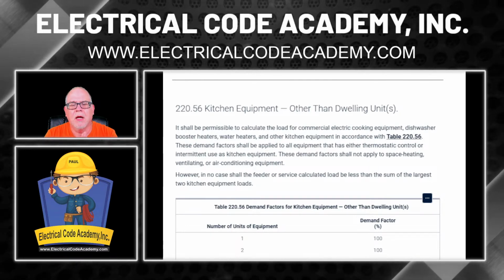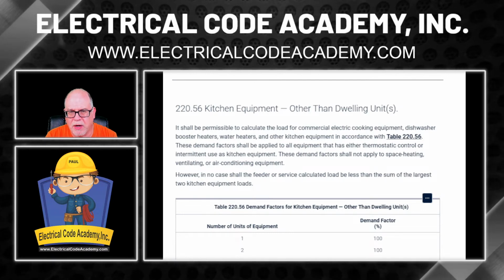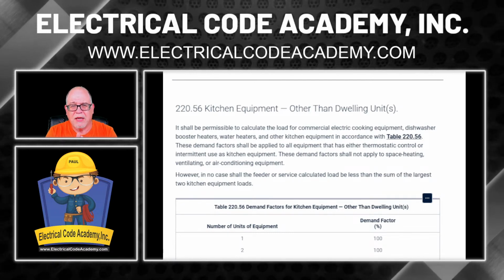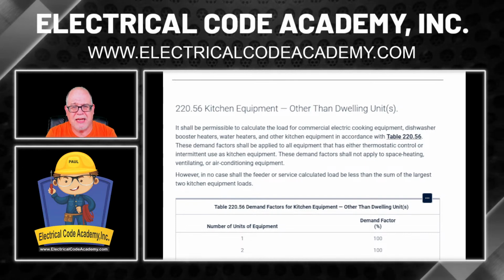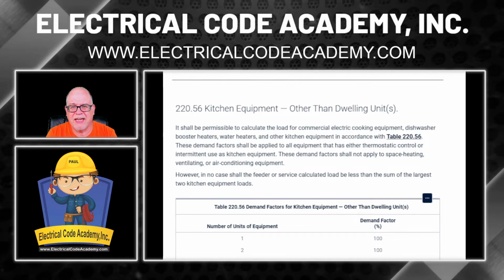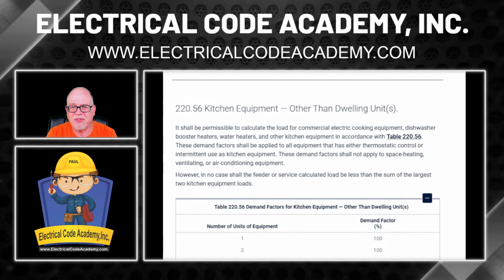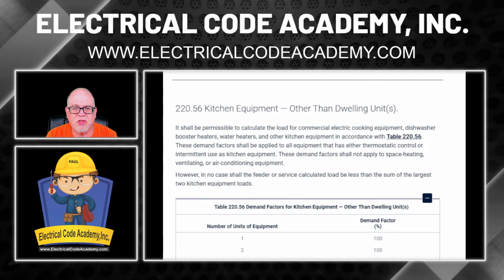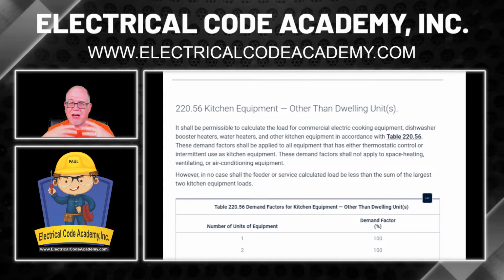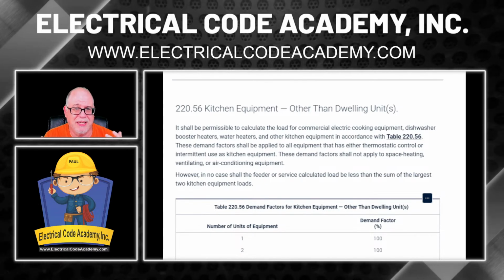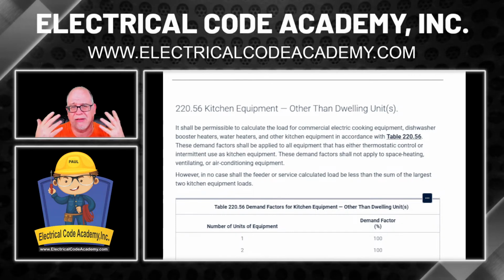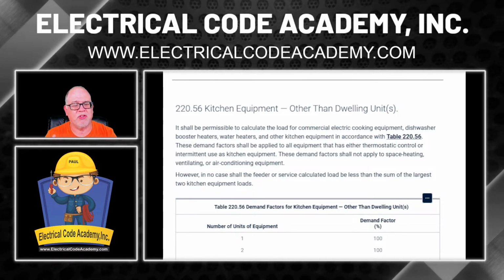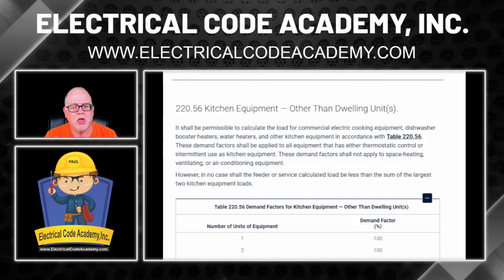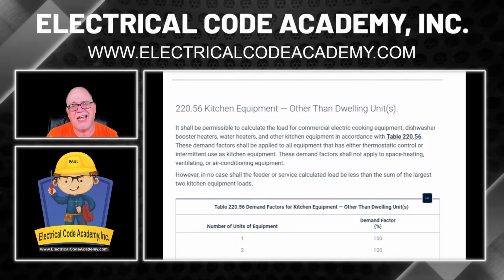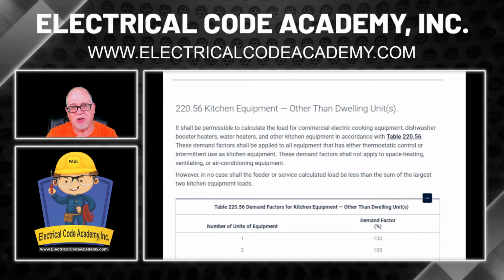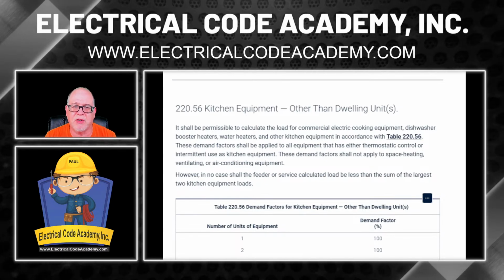Okay. One of the most important aspects I want you to be aware of is where it says, however. It says, however, in no case shall the feeder or service calculated load be less than the sum of the largest two kitchen equipment loads. Now, in the full calculation, it's probably never going to be, because we haven't even taken the other loads in the building into consideration. But in this question, based on your contribution, you also have to understand that it can't be less. The math we're getting ready to do can't be less than the two largest pieces of equipment.